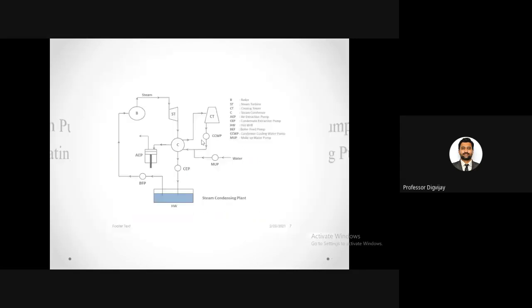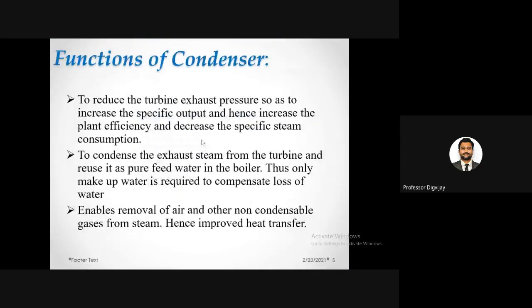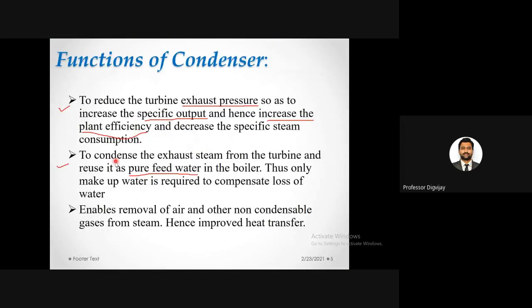So we'll go back to what we were seeing. So we were at these functions of the condenser. So here I was explaining the second function. So the second function was to condense the exhaust steam from the turbine and reuse it as pure feed water in the boiler. Okay. So we have this boiler feed pump which takes the water from the hot well and it supplies to the boiler. So thus only makeup water is required to compensate the loss of water. So if there is any loss in the system, we are going to use the makeup water.